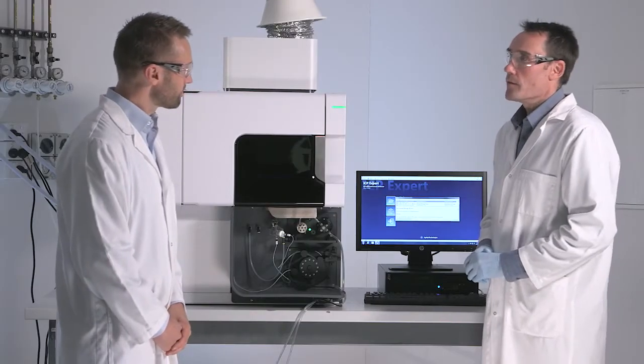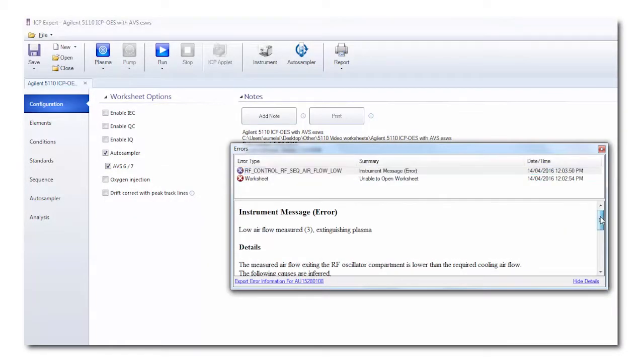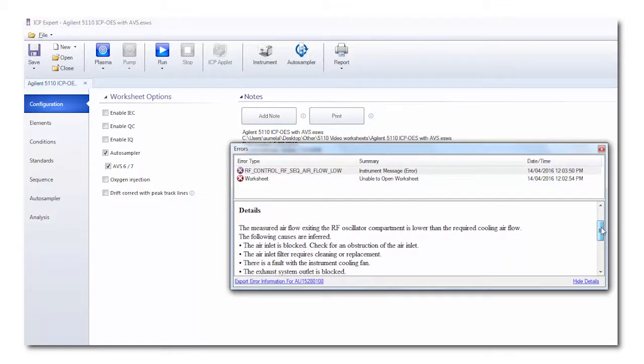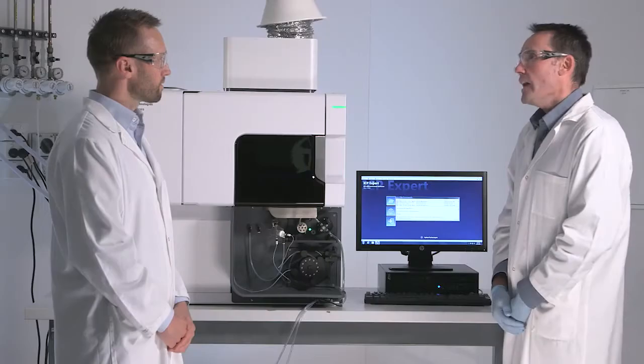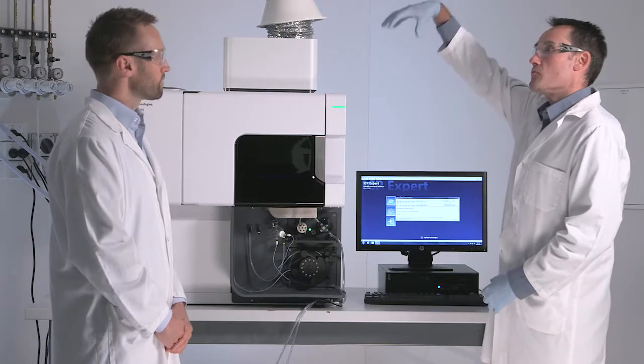Another new feature of the 5110 is enhanced diagnostics. We have multiple electronic sensors distributed all throughout the instrument to rapidly give information back to the operator about what's happening inside the instrument. Those sensors feed back information through to actionable error messages, and it also feeds back information to a new graphical interface called the dashboard. So I notice there is an error message on screen with a low airflow. Airflow comes in the fresh air intake, which is right up on the top of the instrument.